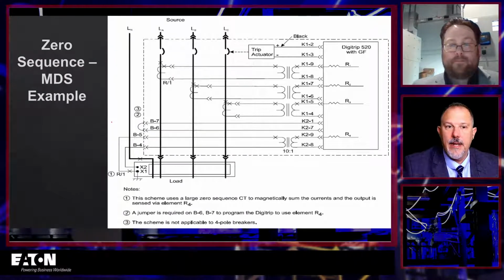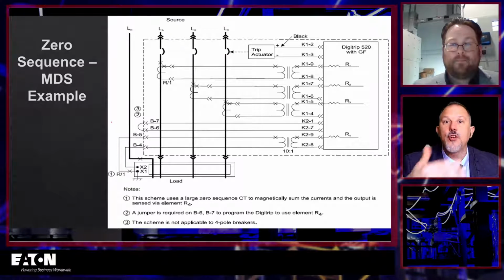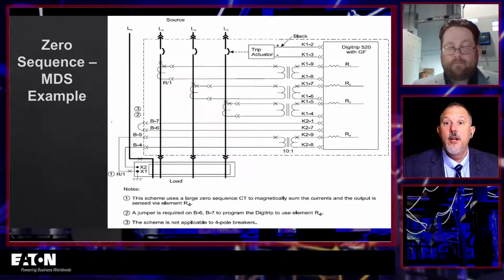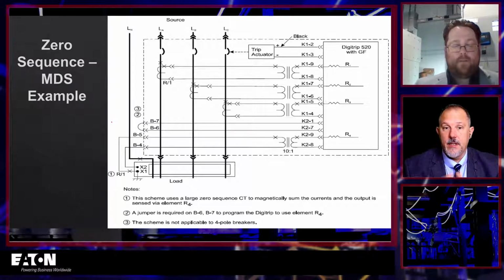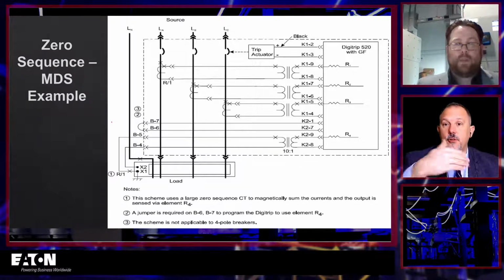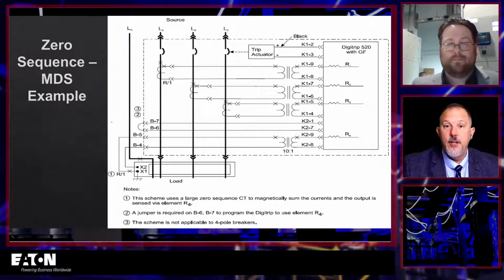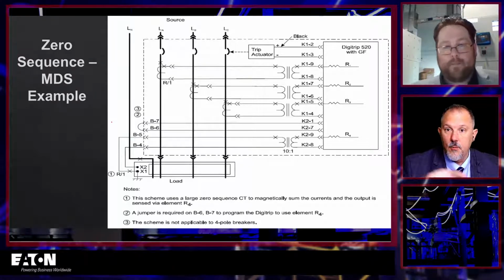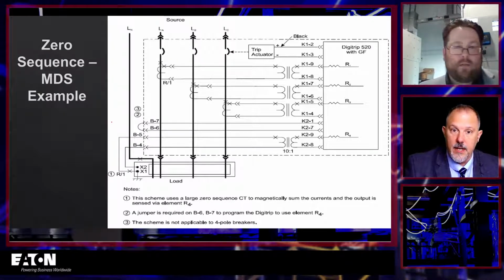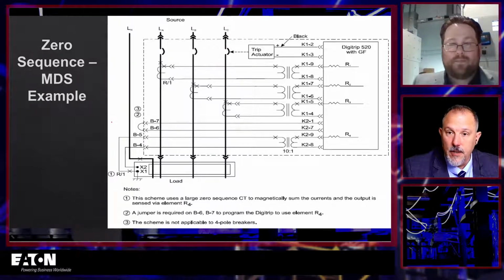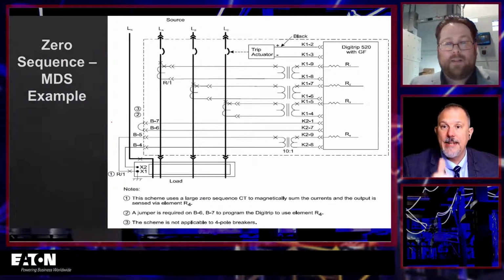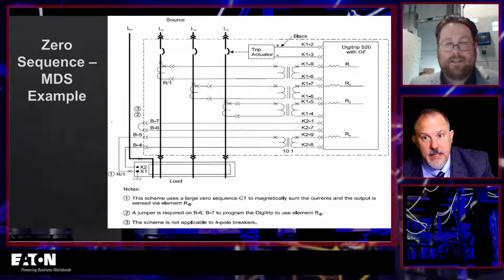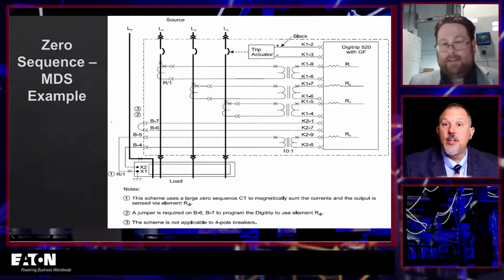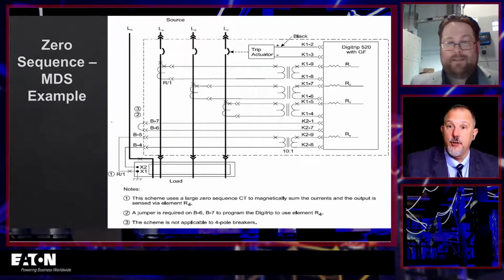In some cases, the manufacturer will put their CTs in there in the gear, so to speak, and will make sure that it's all matched. But if you're retrofitting or you're doing something in the field separately, you've got to think about the burden, how many different relays you're hanging off of this thing. You've got to think about the CT ratio. You've got to make sure it's a relaying class CT as opposed to a metering class CT from an accuracy standpoint, and that goes to saturation on how much current you're expecting to see.